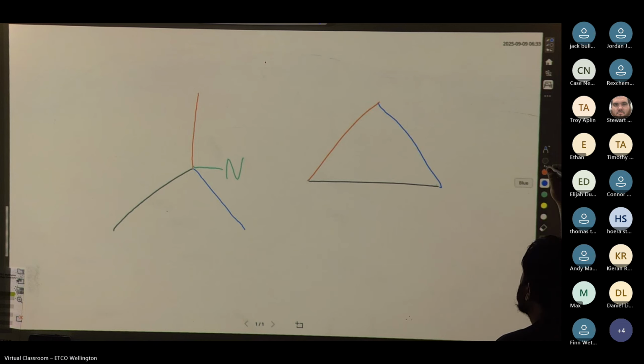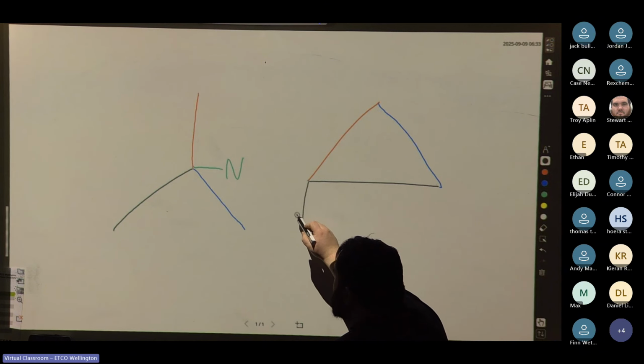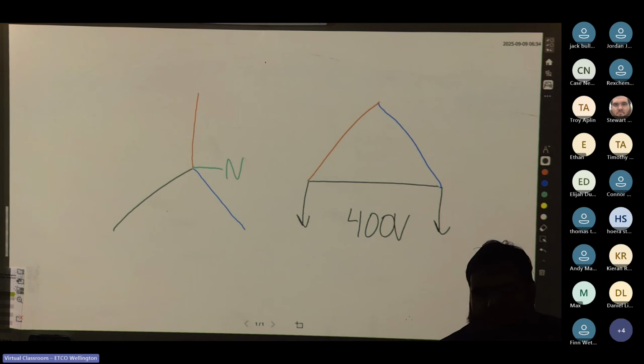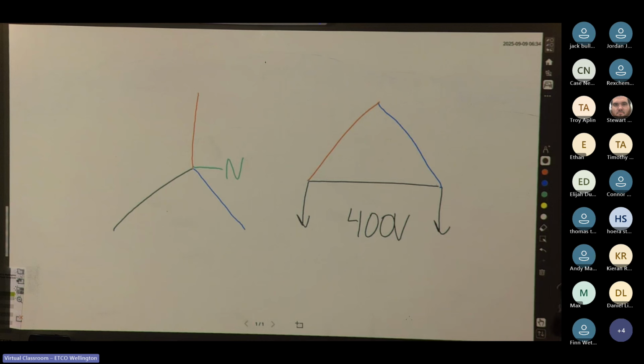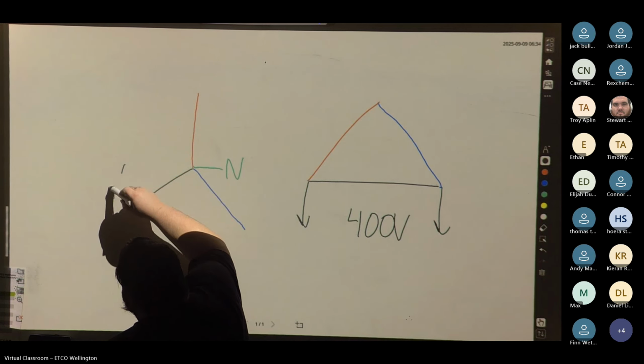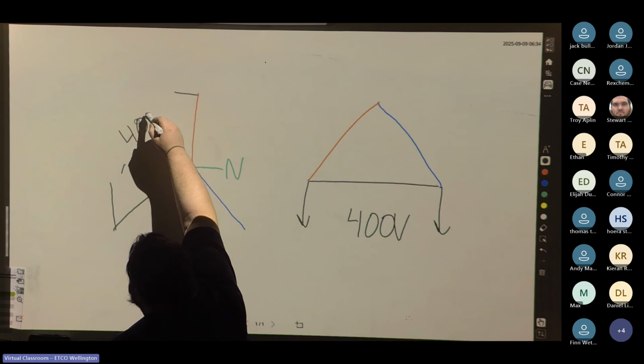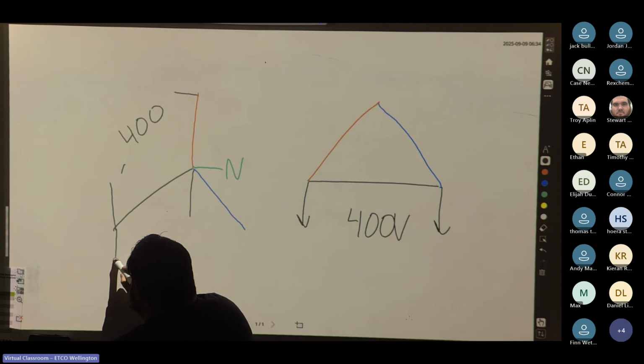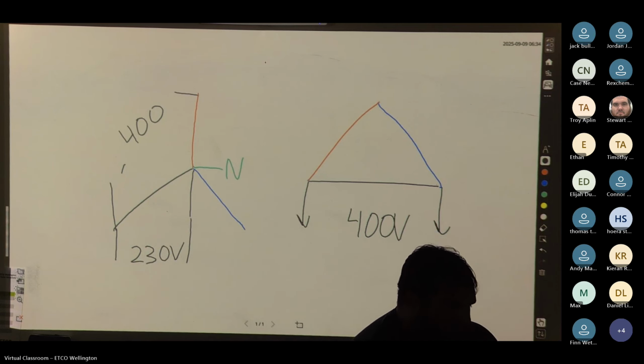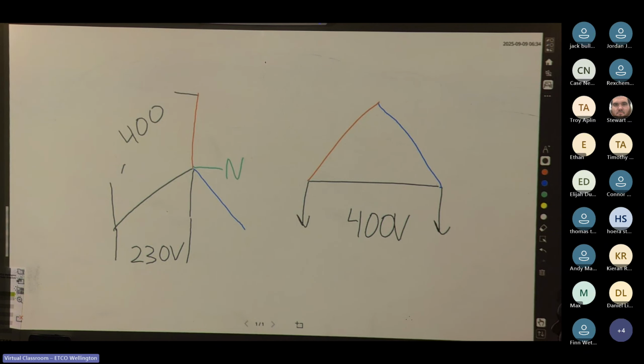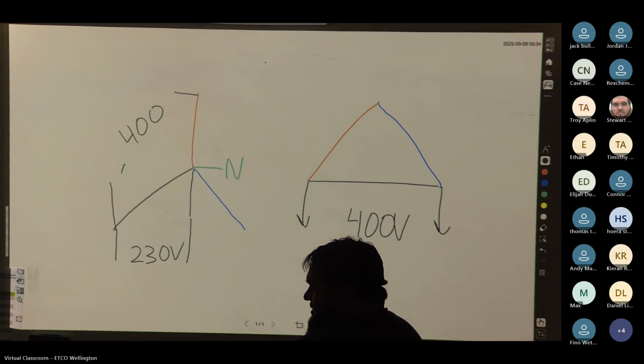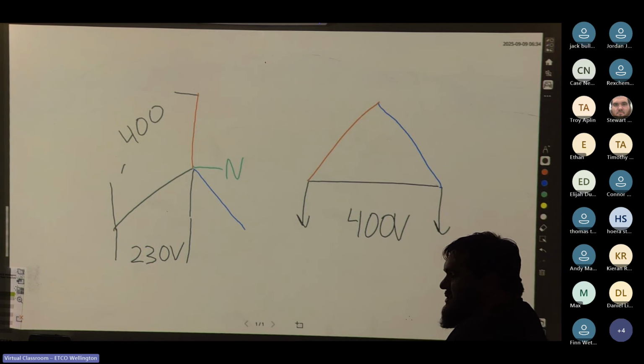So, go back to black. Between this point and this point, we have 400 volts. Standard low voltage, standard 3-phase. That gives us our 400. Between these 2 points here, we have 400 again. But between our neutral and the other end of our winding, we have 230 volts. So whenever we're dealing with delta, it's always 400 volts. When we're dealing with star, it's 400 volts between phases and then 230 from phase to neutral or across one winding of the transformer. We will look a bit more in detail about transformers later, but for now, we're just talking about the national grid supply.